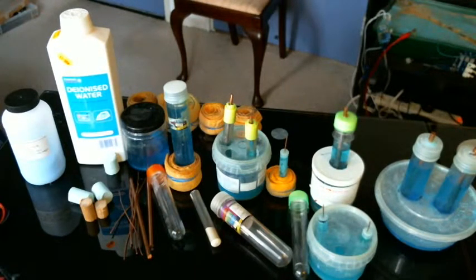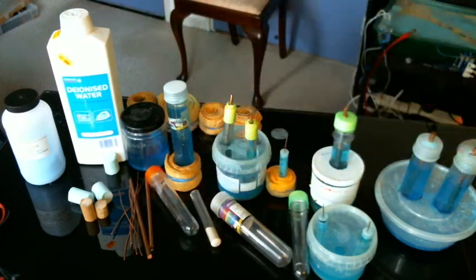A copper sulphate electrode is sometimes called a reference electrode, abbreviated to RE. Sometimes it is called a copper sulphate electrode, abbreviated to CSE, and is known commonly as a half cell. It consists of a copper rod in a saturated solution of copper sulphate contained in a tube with a porous plug at the end that can make electrical contact with the ground and complete a measuring circuit.